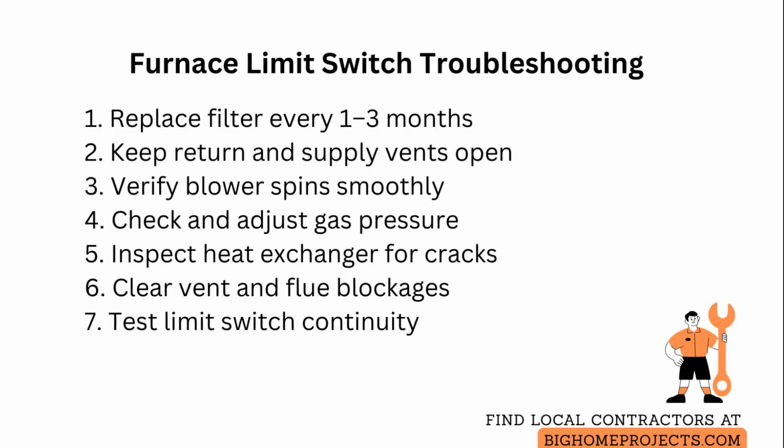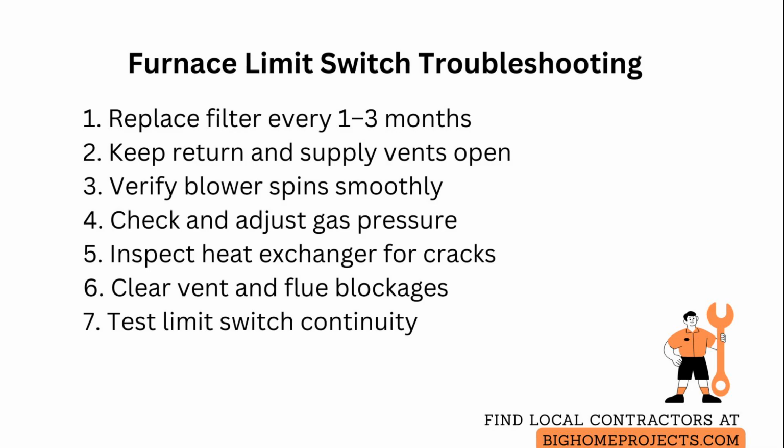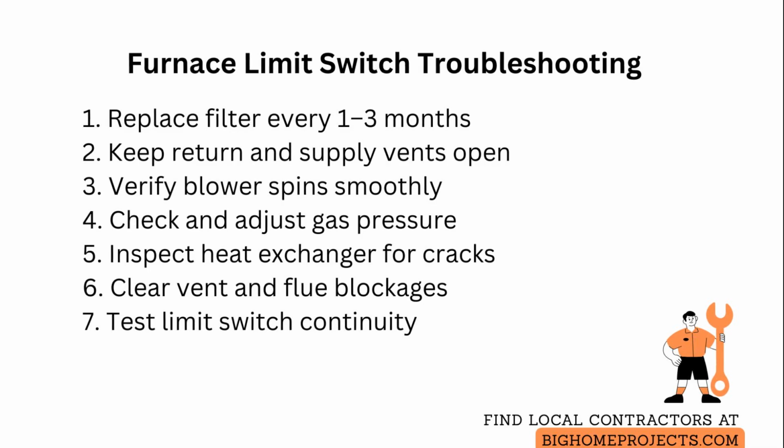Finally, a faulty limit switch, corroded wiring, or loose connections will create nuisance trips, so test the switch for continuity at operating temperatures and replace connectors or the switch if readings are inconsistent.